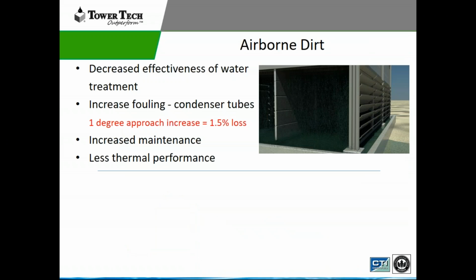So let's talk about some of the traditional issues. When we look at airborne dirt on a cooling tower, the cooling tower is basically an air scrubber. We have a fan that's moving air across fill, and it's grabbing the dirt that's all around that cooling tower and sucking it in, and we're discharging it out. At that point we need water treatment to effectively treat that dirt. But eventually that dirt ends up on the condenser tubes in the chiller. And if we lose 1 degree of approach on that chiller, it decreases the chiller efficiency by 1.5%. That may not seem like a lot, but we're talking about a big horsepower motor in that chiller plant. So a 1.5% loss is a big deal.